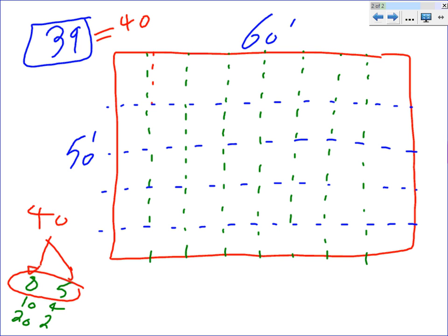we're going to end up with how many? 40? Is that 40, guys? 8 times 5. So then you go to the center of every rectangle that you did, and you put your fixture right at the center. Here's my center.